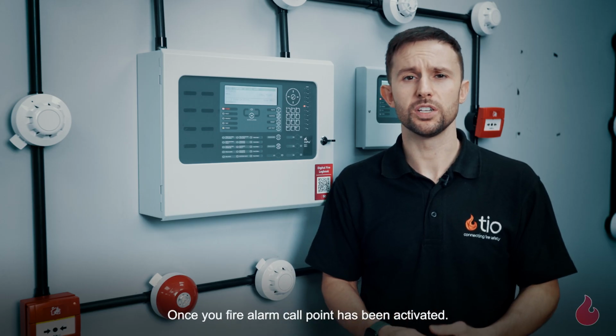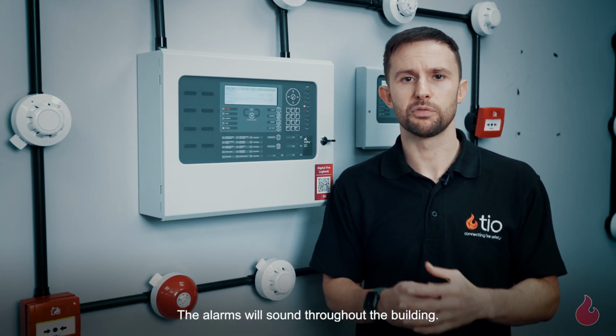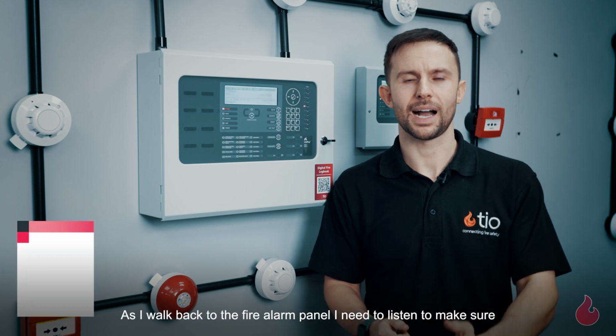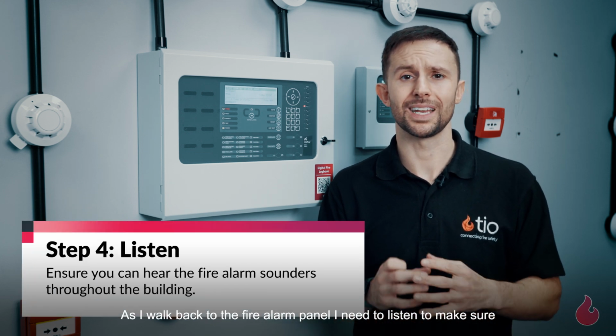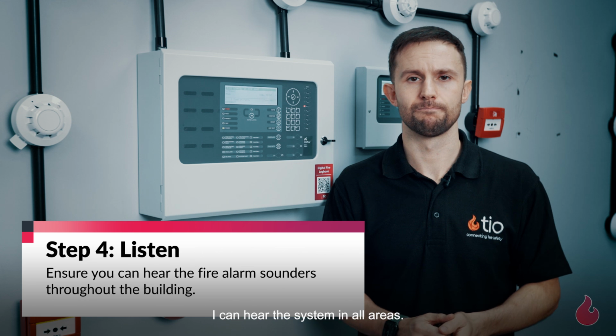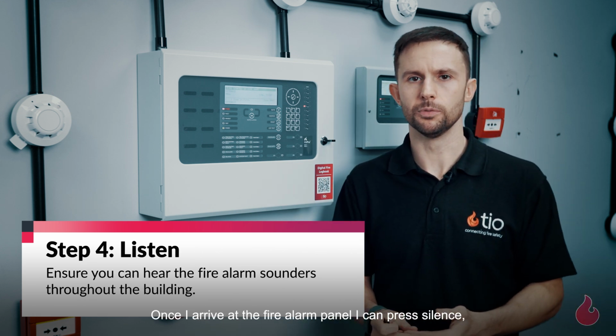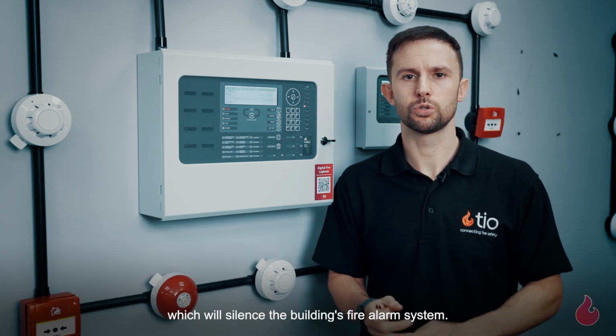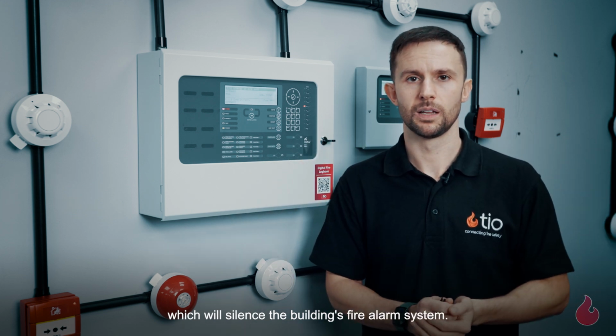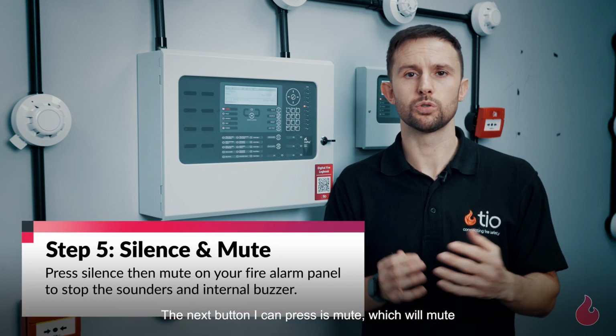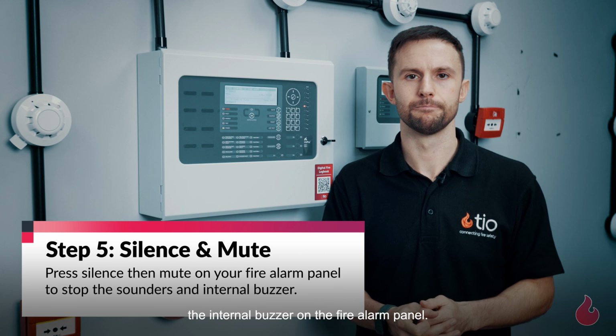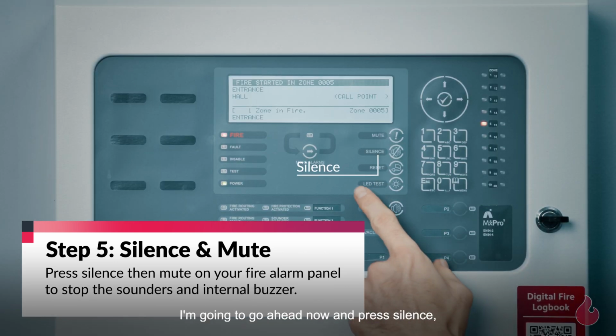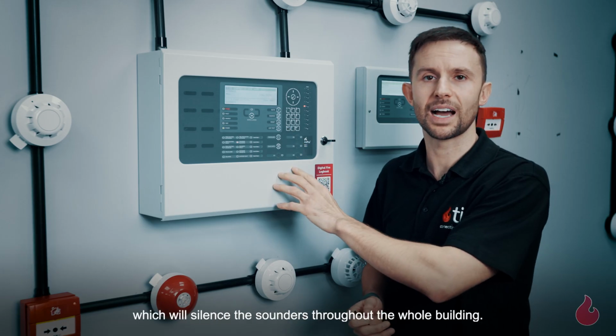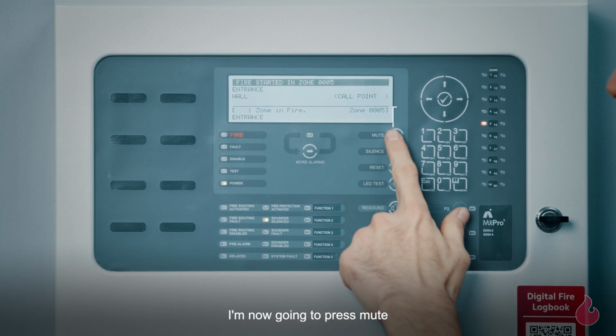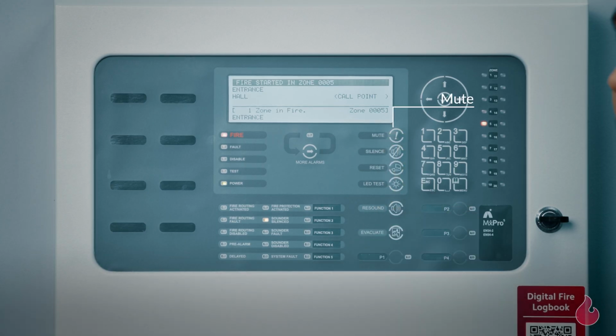Once your fire alarm call point has been activated, the alarms will sound throughout the building. As I walk back to the fire alarm panel, I need to listen to make sure that I can hear the system in all areas. Once I arrive at the fire alarm panel, I can press silence, which will silence the building's fire alarm system. The next button I can press is mute, which will mute the internal buzzer on the fire alarm panel. I'm going to go ahead now and press silence, which will silence the sounders throughout the whole building. I'm now going to press mute, and this will silence the internal sounder in the fire alarm panel itself.